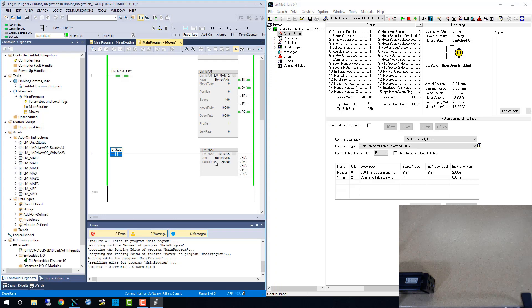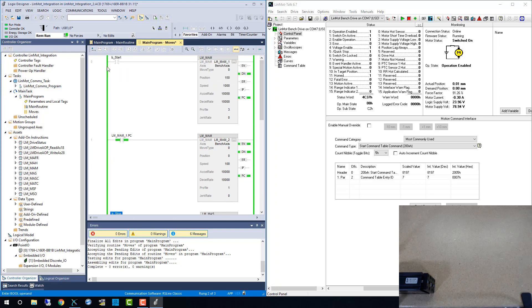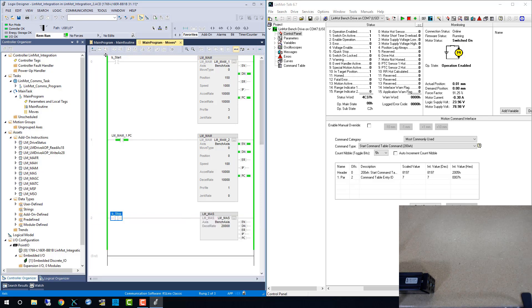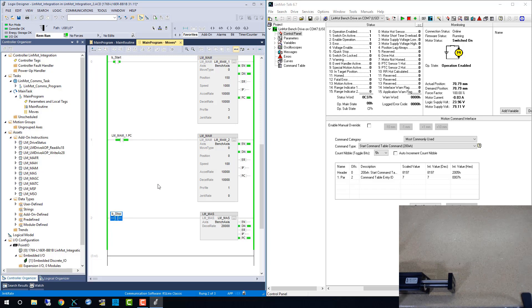Now back to LinMot talk and the webcam, and we can watch the motor extend and then stop on the retract move. Once we stop, you will notice the actual demand position are set to the same value, but the LinMot doesn't apply any more current to hold this position.